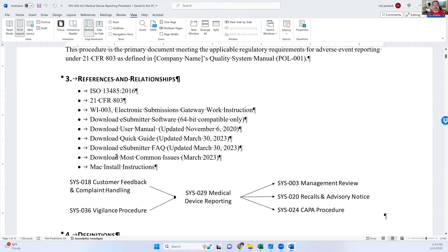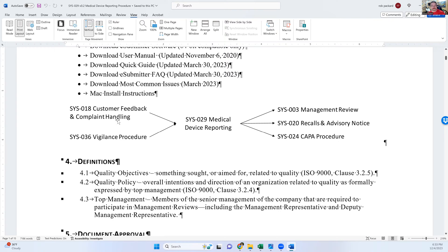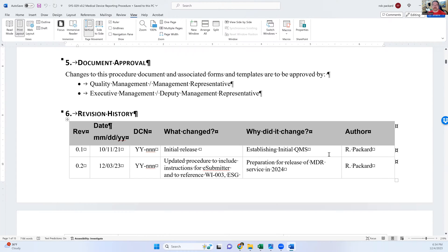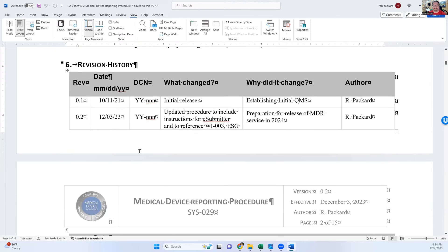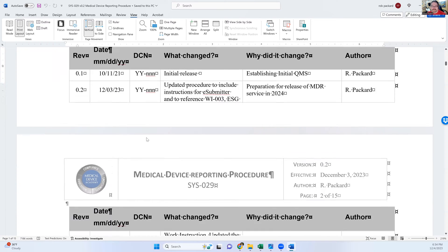I've added a lot more references — those references to the documents I've included in the bundle. We're using the same flowchart: customer feedback and vigilance reporting as inputs, and your incident reporting procedure could also be an input if you do Canadian licensing. Outputs include management review, recalls, and advisory notices. We've updated the revision history to be more specific — rather than just a generic version, we're going to tell you exactly what we changed. I'm trying to go back retroactively to identify what previous versions were wherever practical.